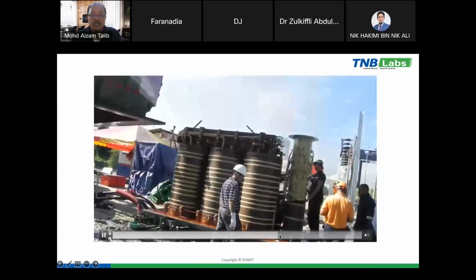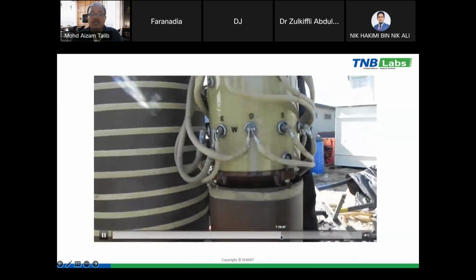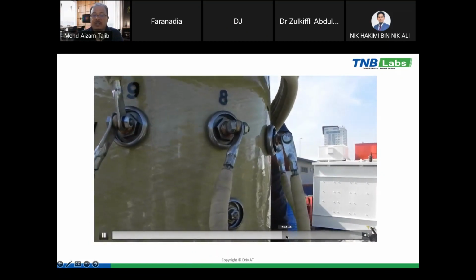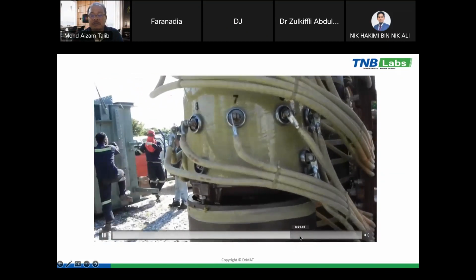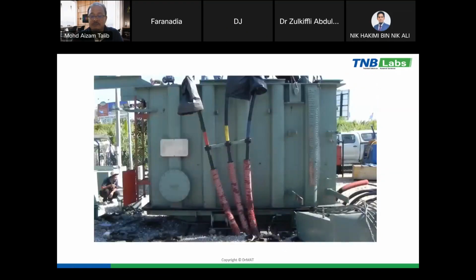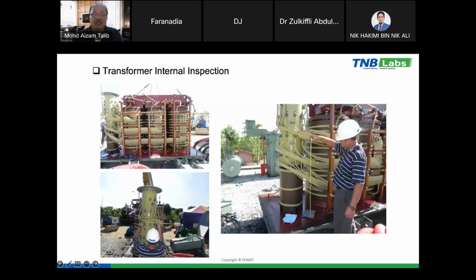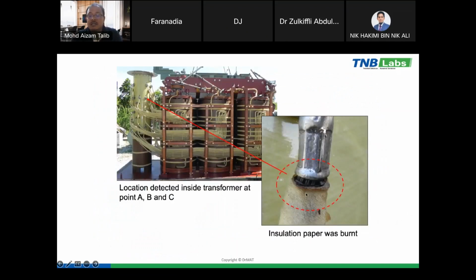So we measured again with the acoustic measurement to find the possible location of the fault. So finally, what did we get here? Okay, there is a poor terminal connection between the winding and the tap changer. The terminal has been burned. We can see there is an arcing sign here, an overheating sign here, and the insulation paper has been burned. So this is the cause of why it generated fault gases in the power transformer.